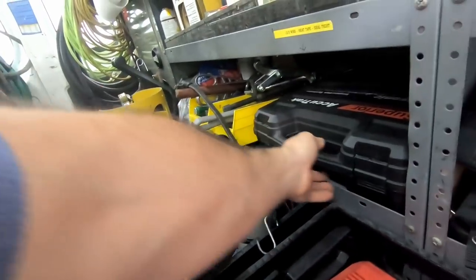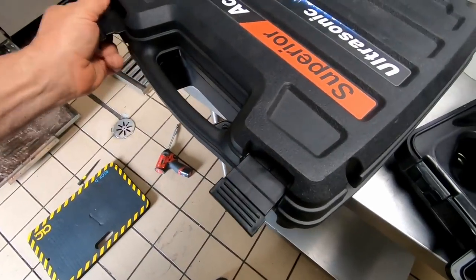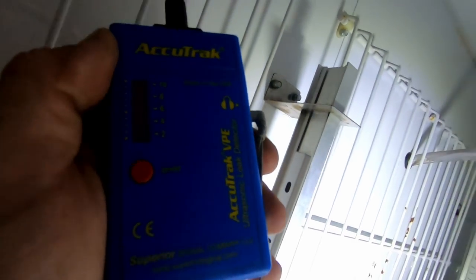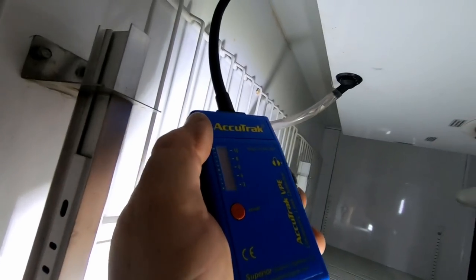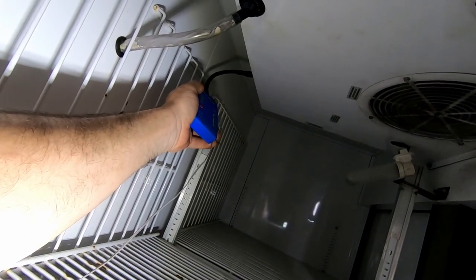We've got the Whisper and the AccuTrak leak detectors - let's give them both a shot. It was making a popping noise in here when I was standing here for a second, but now I'm not hearing it - just a random pop. This is where the gooseneck really comes in handy to get back in tight areas. Usually the noise is going to bounce around. I'm not hearing any real hissing or squealing.